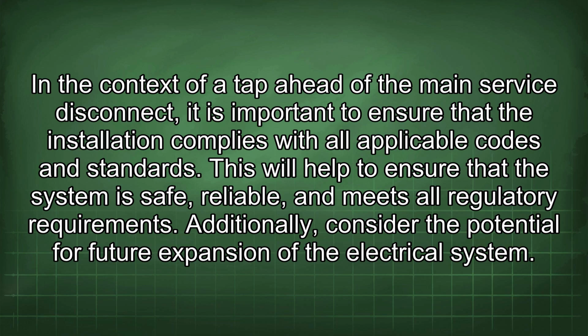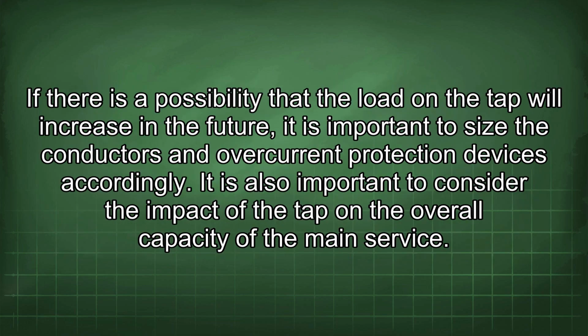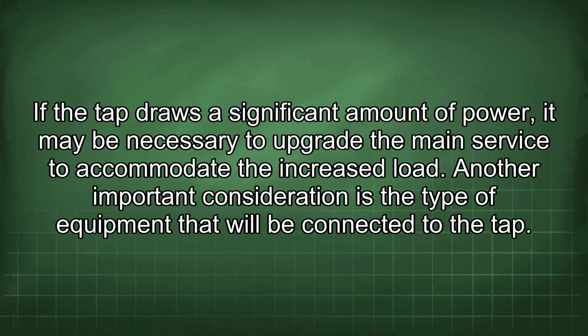Additionally, consider the potential for future expansion of the electrical system. If there is a possibility that the load on the tap will increase in the future, it is important to size the conductors and overcurrent protection devices accordingly. It is also important to consider the impact of the tap on the overall capacity of the main service. If the tap draws a significant amount of power, it may be necessary to upgrade the main service to accommodate the increased load.